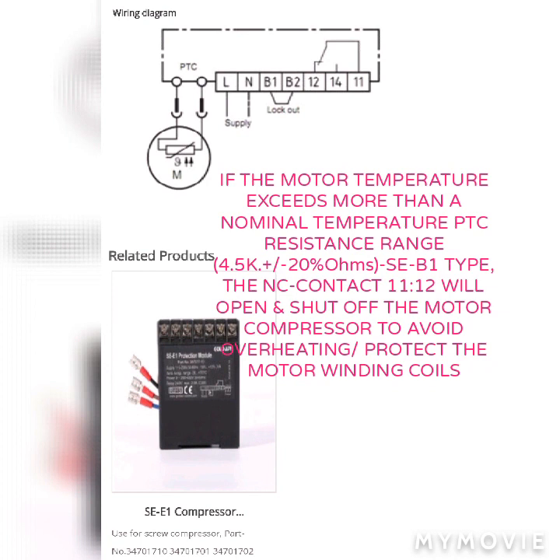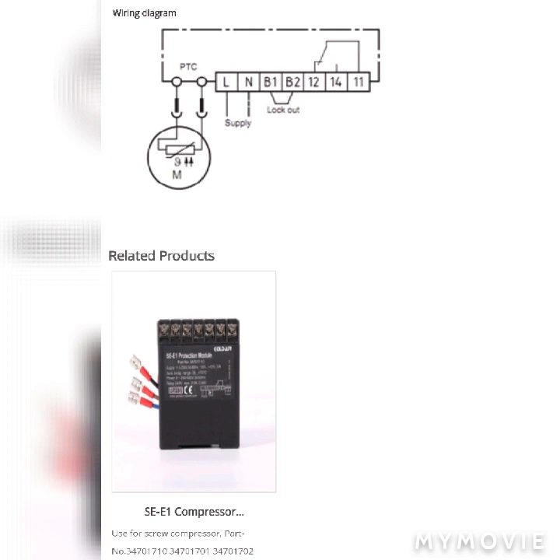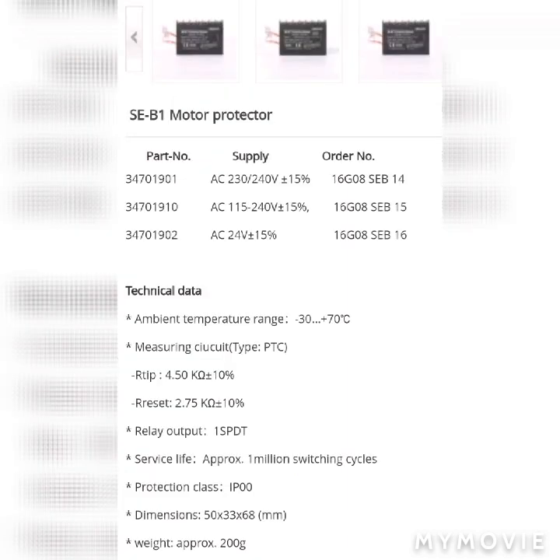Here I have a new motor protector of SE-B1 type, and I'm going to simulate it by following the wiring connection here and identify the equivalent resistance with motor temperature at which the normally closed contact 11 and 12 changes from close to open, and from open to close.